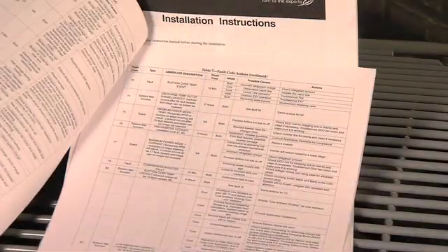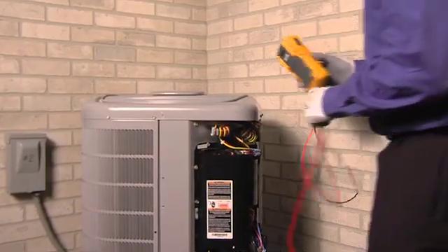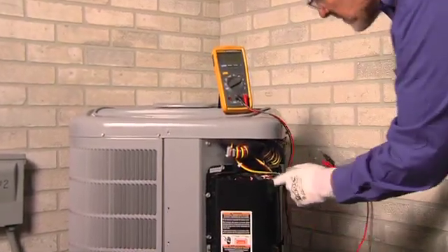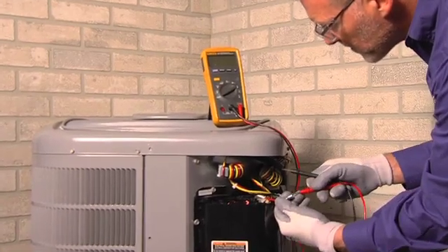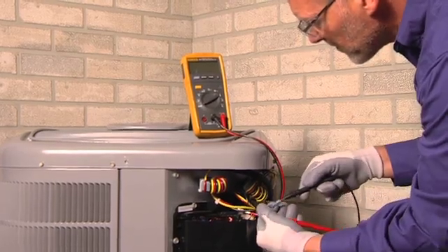There is no reason to use a multimeter to check inverter output to the compressor or fan motor. That's because there are no published values of these voltages versus the compressor or fan motor RPM. If the compressor and fan motor will not operate, use the fault codes to diagnose the possible reason. If the compressor and fan motor will operate, the inverter output is good. A multimeter should be used to check the winding resistances in ohms between the phases or ground of the compressor and fan motor, if they are suspected of being defective. The service manual has the appropriate resistance values.